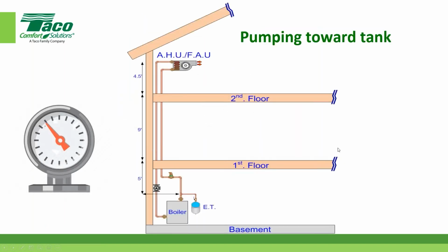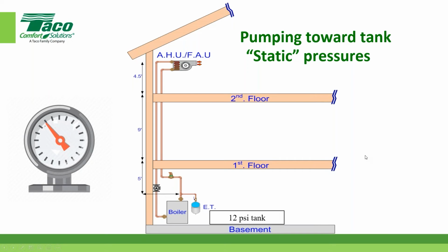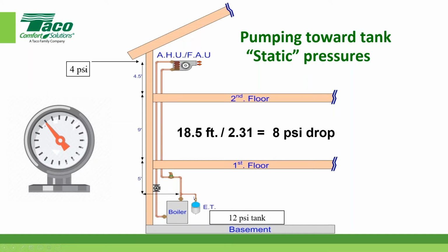Okay. So here's another analogy. I'm going to go pretty quick now, but I think you'll get the point. If the system's not doing anything, it's in a static condition. I've got 12 psi on the air side of this tank, and I end up with 12 psi starting out as a static condition. I measure this 18.5 foot. I divide it by that number we showed you earlier, 2.31, because that turns it back into psi. I'm going to have an 8 psi drop up here at the top of this air handler. Everybody okay with that? If I started at 12 and I go all the way up here and measure the pressure, if I had the ability to measure it here, I would see that it dropped 8 psi. What's 8 from 12? Well, then you got your answer. You're going to be 4 psi, which is fine. I've got 4 psi up here at that air handler.